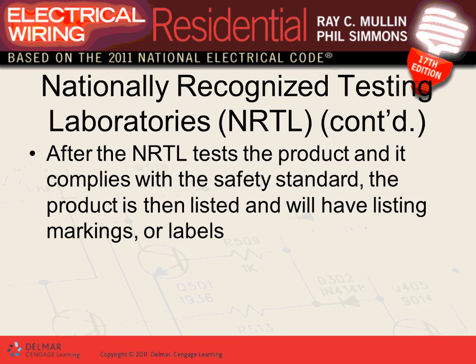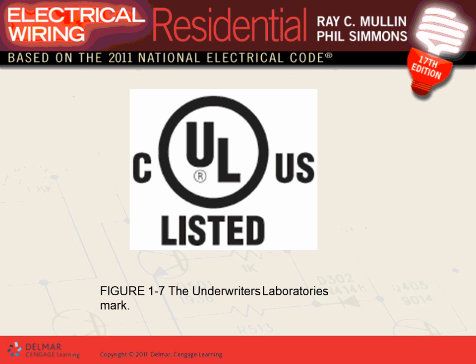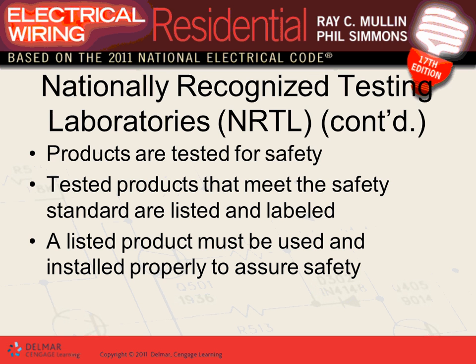What happens if you don't have a UL label in Minnesota? Say you brought a machine from China without one - though honestly the Chinese know about UL too, so they're usually smart enough to get a UL label or equivalent. In Minnesota, there are registered electrical engineers you can hire as an owner if you have equipment that isn't listed. Those engineers will analyze the equipment and give you a report equivalent to a UL listing. So that's your alternative to the UL label.